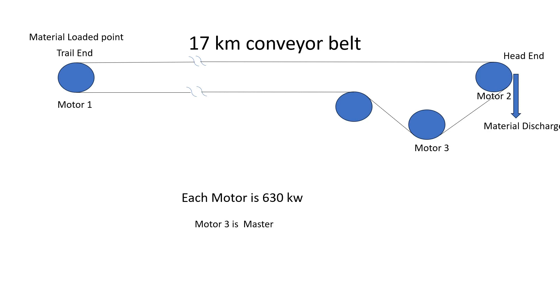Today we will not discuss more about Master-Follower itself — what we are here to discuss is the specific parameter. When we gave a command to run and gave a set point to Motor 3, Motor 3 and Motor 1 were taking high current and high torque. Because of taking high torque, they were taking more load and more current, and the system was tripping. Motor 2 was not taking sufficient torque or current. Why did this happen?